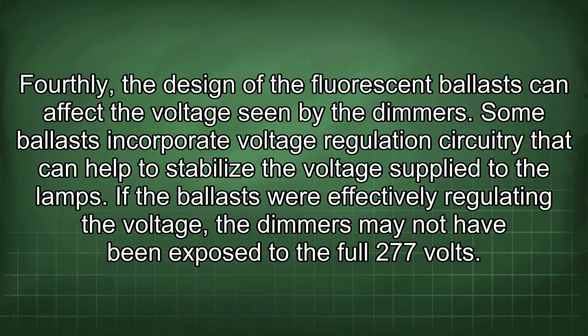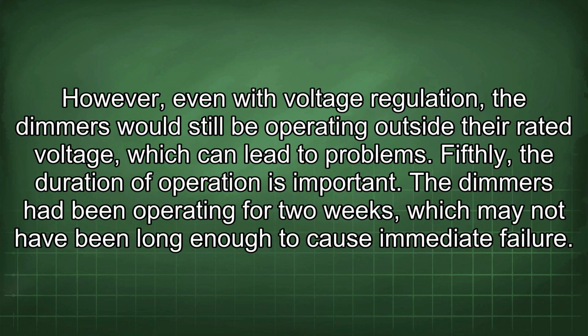Fourthly, the design of the fluorescent ballast can affect the voltage seen by the dimmers. Some ballasts incorporate voltage regulation circuitry that can help to stabilize the voltage supplied to the lamps. If the ballasts were effectively regulating the voltage, the dimmers may not have been exposed to the full 277 volts. However, even with voltage regulation, the dimmers would still be operating outside their rated voltage, which can lead to problems.